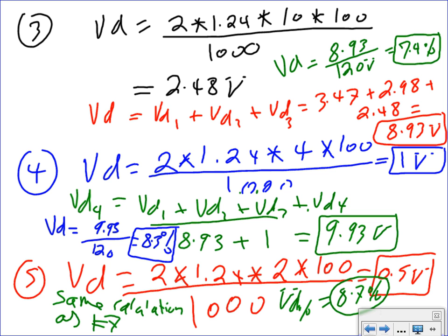Any questions, guys? Two things you get out of this example. Number one is never use number 10 in a parking lot that large. Number two is never use 120 voltage in a parking lot like that. 120 is the least productive voltage system that you can use.